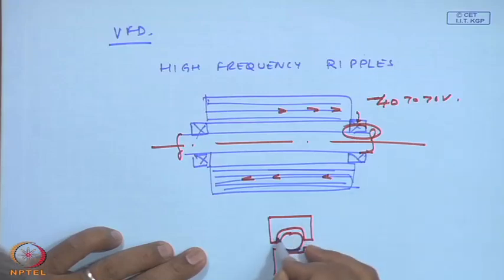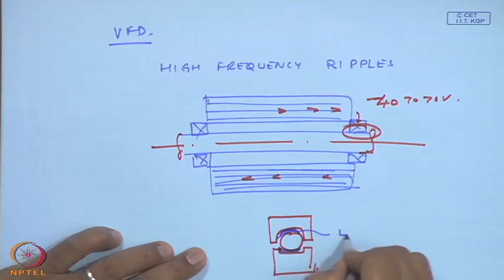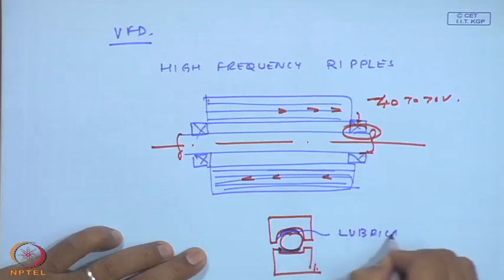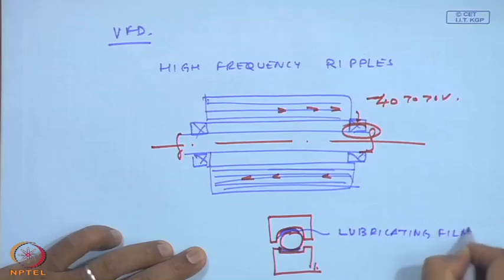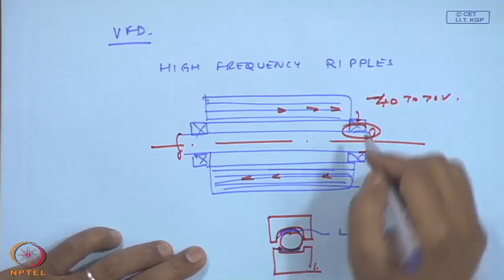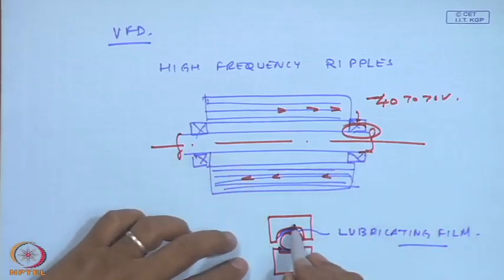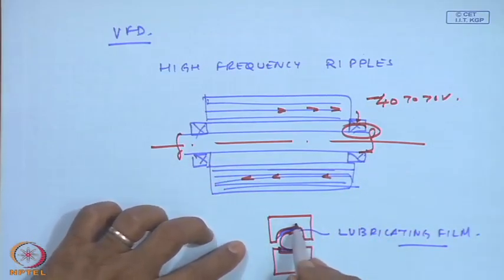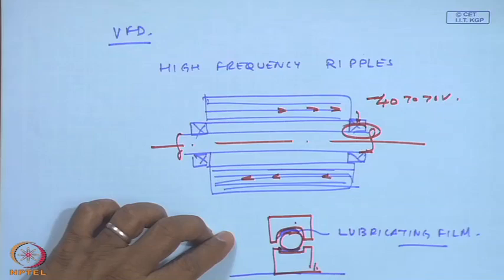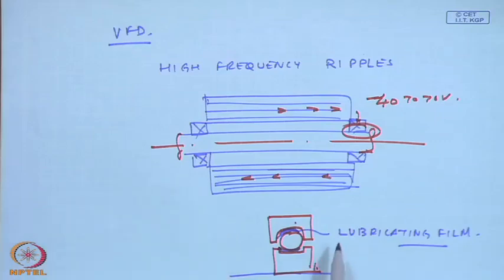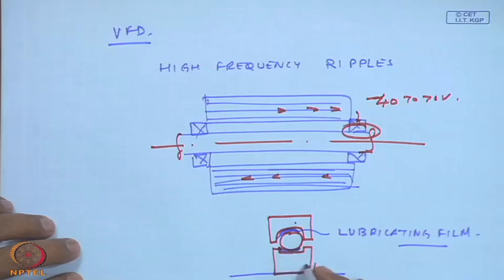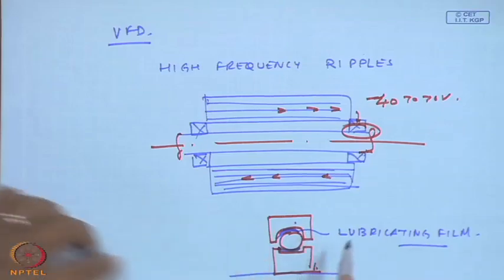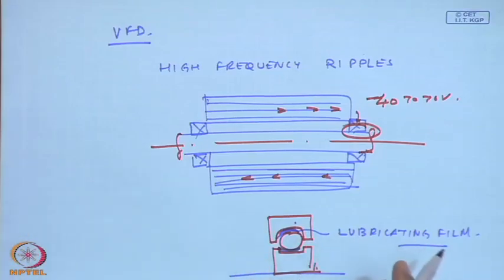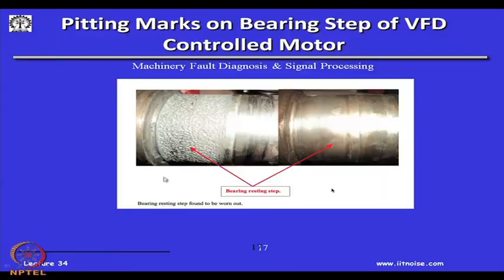There will be a dielectric film, which is actually an insulator. So each time the voltage increases, there is actually a spark across this outer race, which is attached to one, and the inner race, which is attached to the shaft. The bearing shaft sits here. So whenever this bearing is sitting, there will be sparking occurring between the bearing and the shaft. This spark is responsible for eroding the shaft.